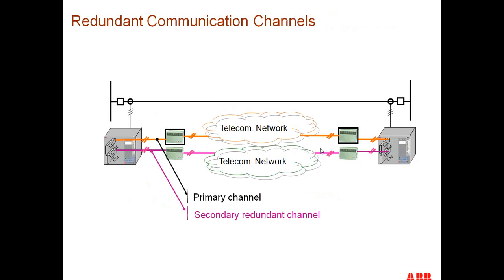Sometimes you might consider using a redundant network where you want to be sure you have a good telecommunications path between one terminal and the other, and you may worry about the telecommunications channel going down for some reason. If that is the case, there are options available so you can have a redundant communication channel running in parallel with the preferred channel, and it doesn't take any action until the preferred channel goes out of service. Then the redundant channel takes over, and it doesn't lose a beat because it's already synchronized with the rest of the system, so it takes over the protection as it is.